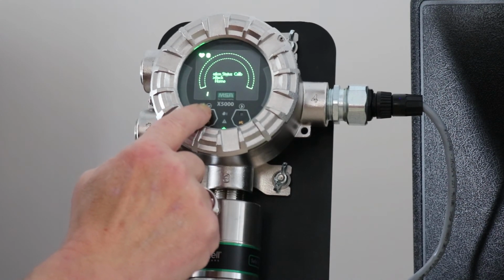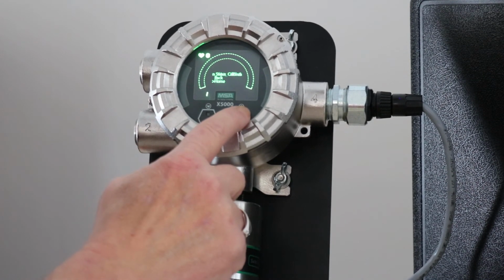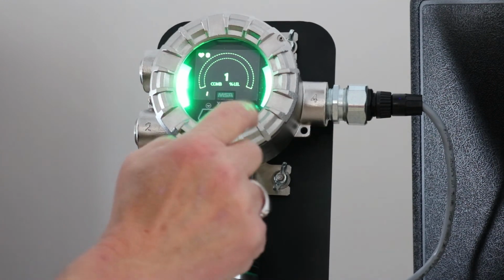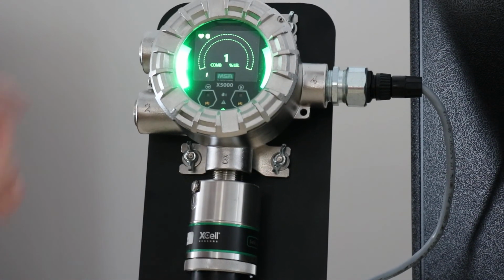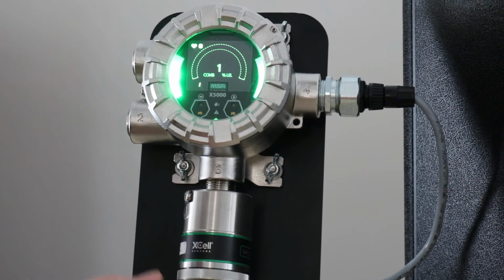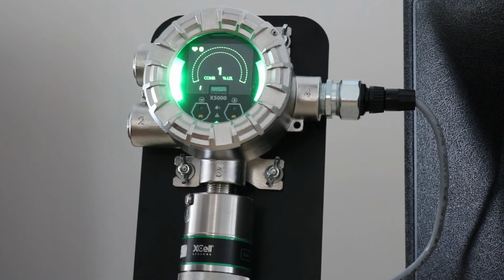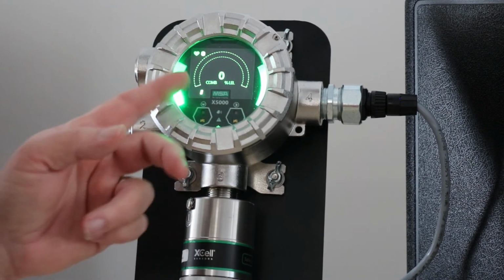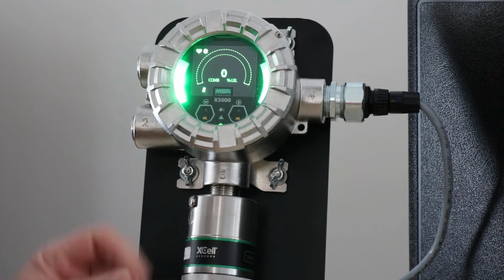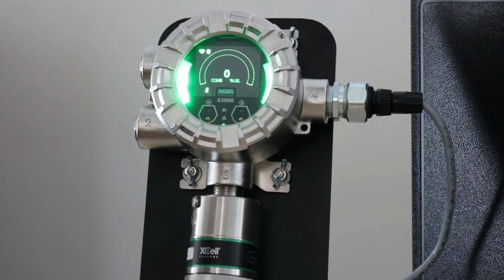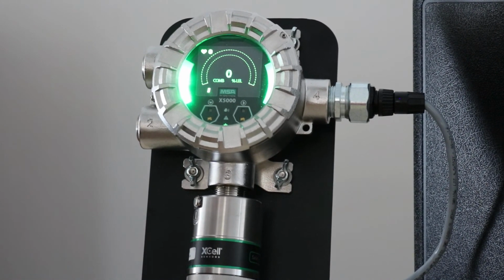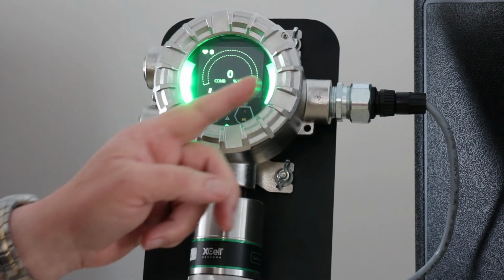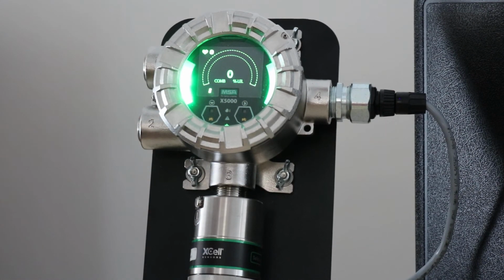Okay, so now we're on the main display. We just go down to home, hit that, and we're back. Now there's a little residual cal gas still in there, span gas, which is why you see 1. Now it's down to 0. And again, the display will go dark in about 3 or 4 minutes probably. Everything else, your LEDs are on and a little heartbeat is going.